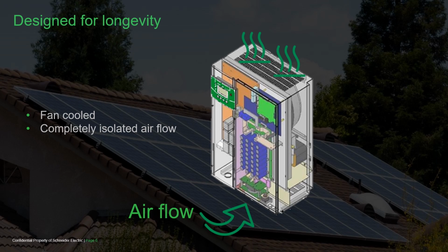Part of the reason is due to the isolated compartment for airflow, which is unique to the XW platform. Dust can accumulate on circuit boards over time and inhibit cooling of components. Some dust may even have conductive properties that may lead to premature failure.